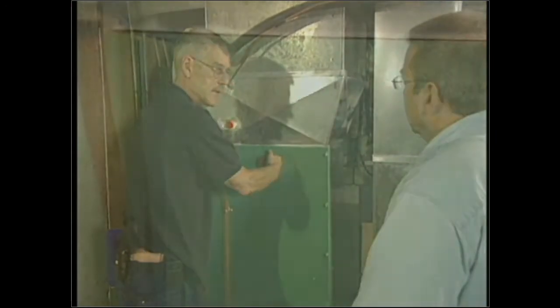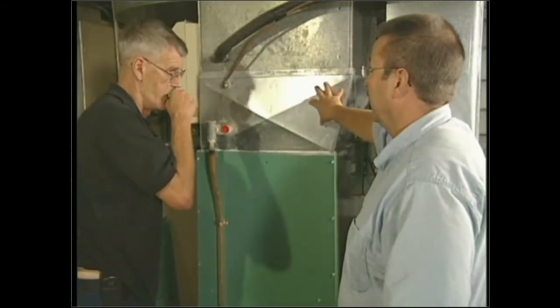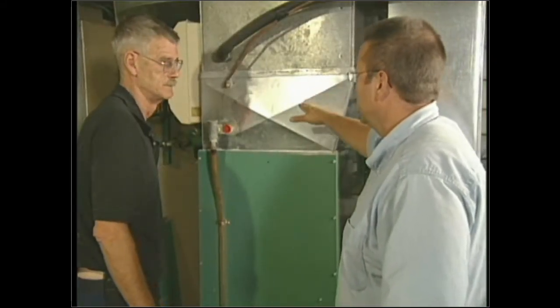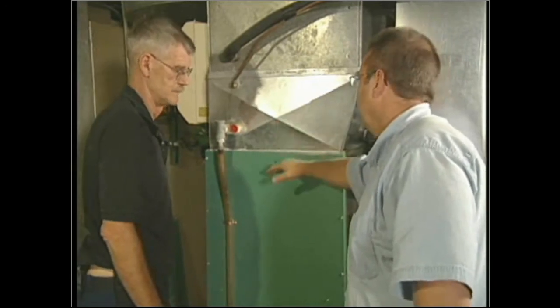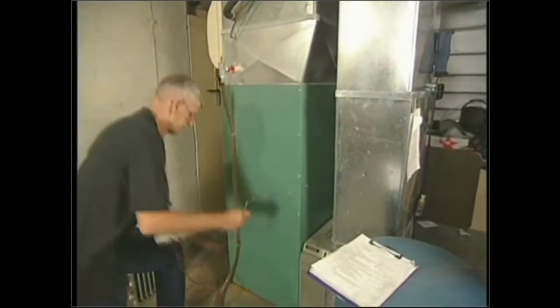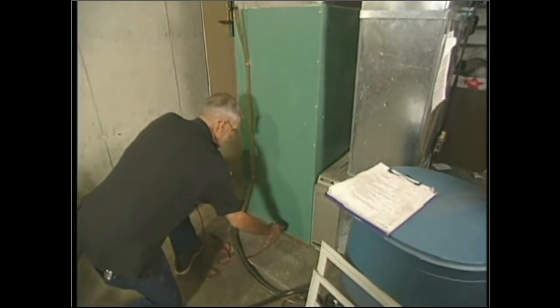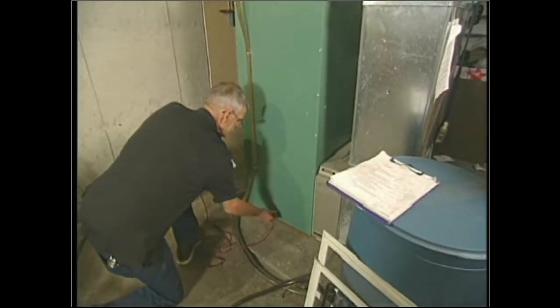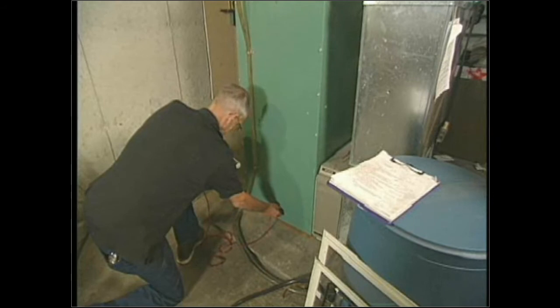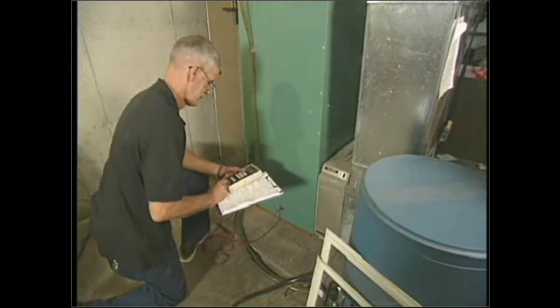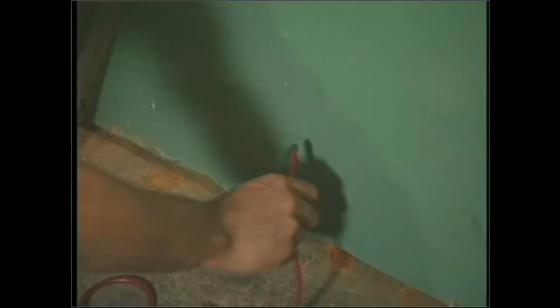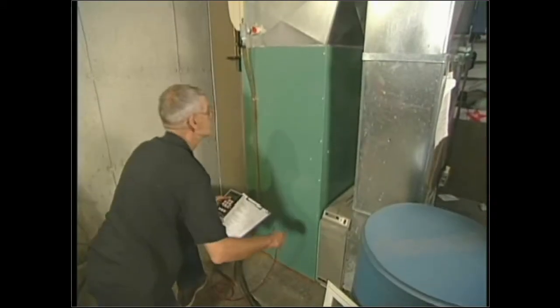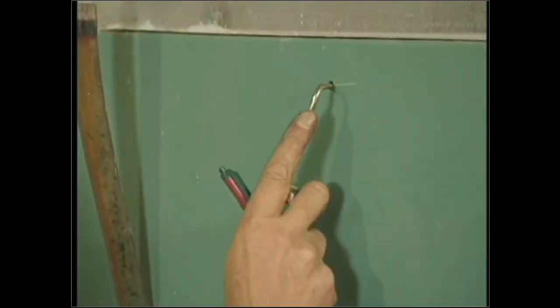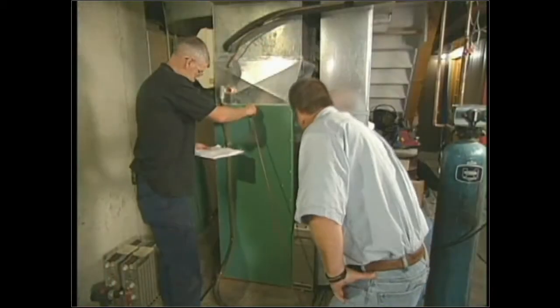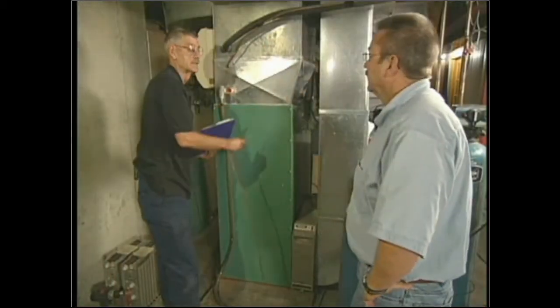the cabinet. And that's a key point for the auditor. Keep in mind, make sure you know whether or not there's an A-coil there. If there is one there, make sure you take precautions not to drill anywhere near that. Just get below it. As we did with the other furnaces, we need to take this static pressure probe. And then what we do is just like we did before. We set up our manometer. We take a reading down here by making sure that our probe is faced in this direction. Then we come up here and go down like this. Because the airflow is coming up, we get it. Airflow goes right around and up. Then we take the two and add them together.